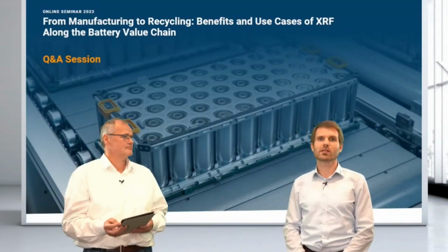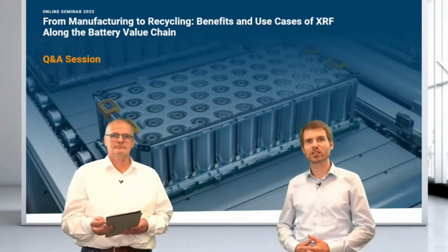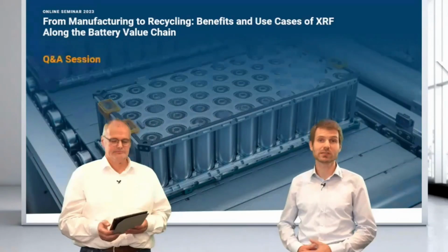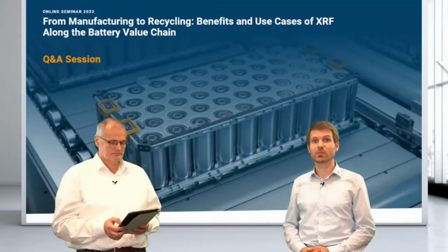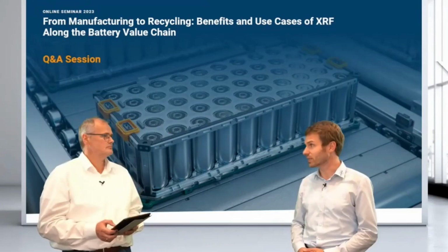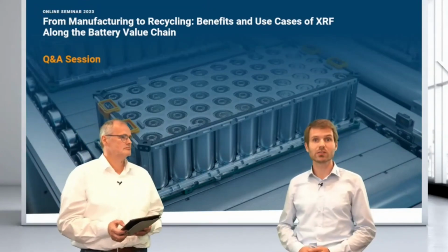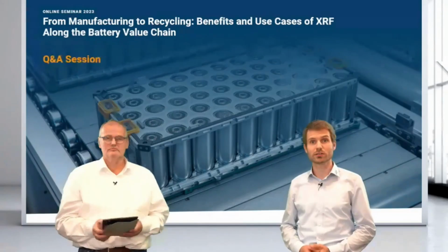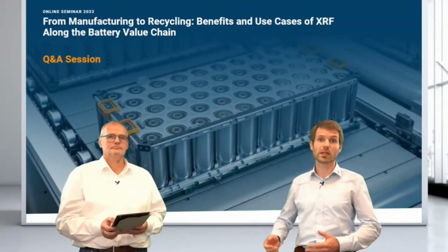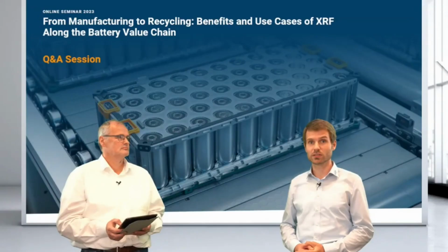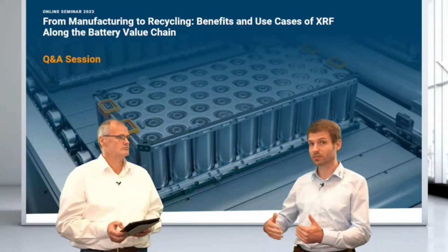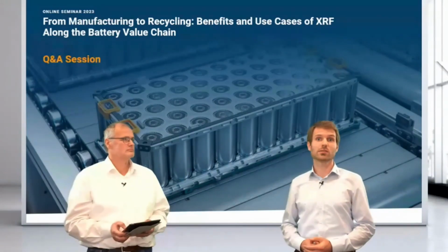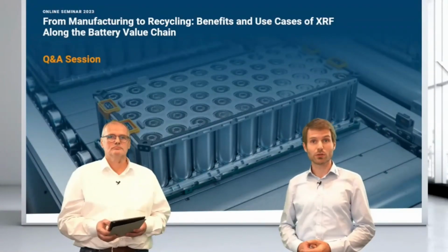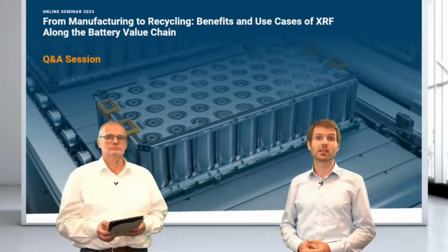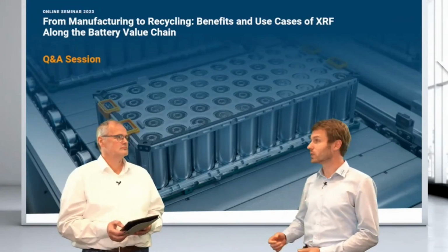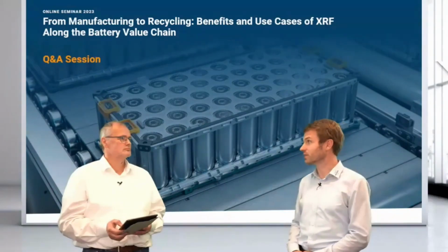So one of the factors is, of course, how much performance you need in terms of trace element sensitivity. But another one can be, especially when you're looking into lighter elements, such as fluorine or sodium, especially at lower concentrations, this is typically where you benefit significantly from a wavelength dispersive system. You have a better peak separation, a better signal to noise ratio. So for instance, if you want to measure residual fluorine in samples or sodium, this could be a good task for S8 Tiger or S6 Jaguar.